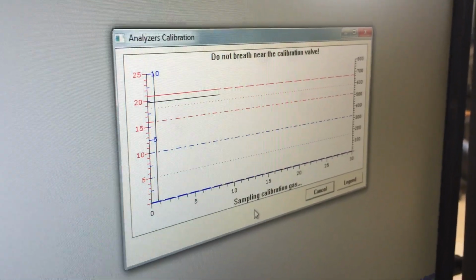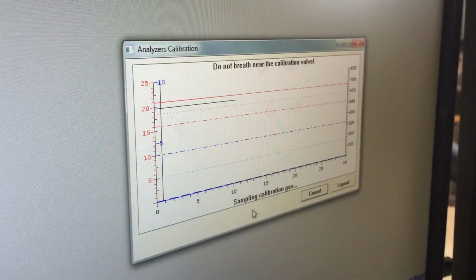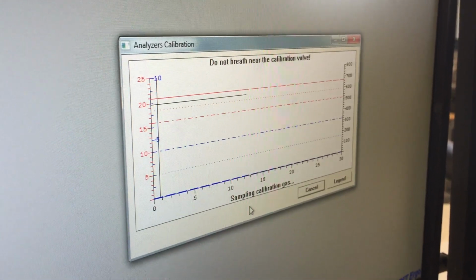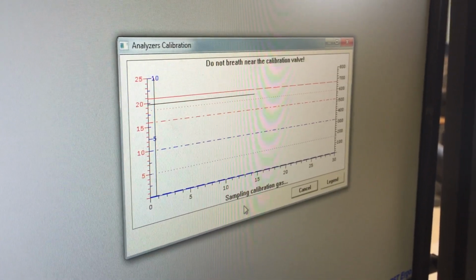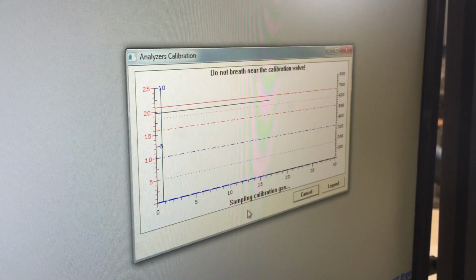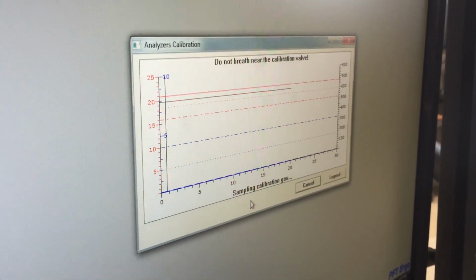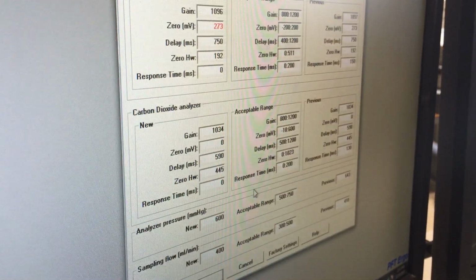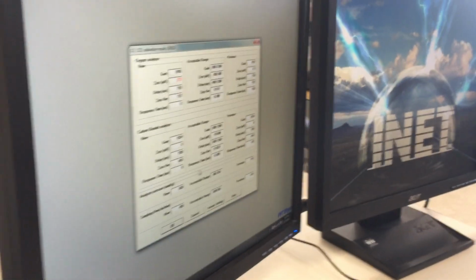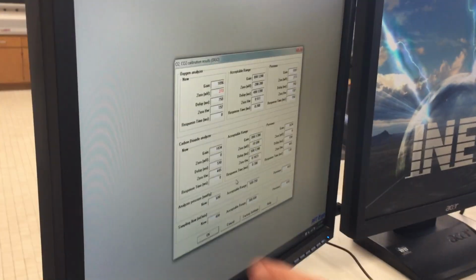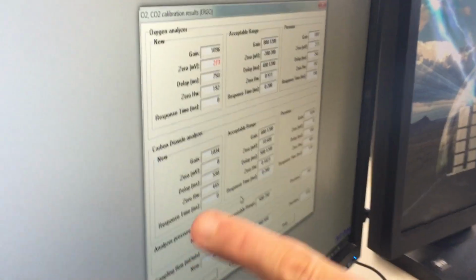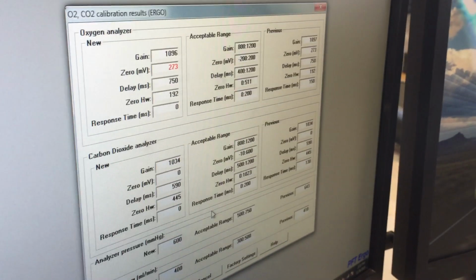We don't mess with the computer at this point. The software does its own thing. Once it gets all the way across, we can move forward. So at this point, we just wait. Again, remember, it takes about 10 to 15 minutes to actually calibrate the equipment from start to finish. So if you're taking that into account with the fact it takes 30 minutes for the unit to actually warm up, you need to make sure you give yourself adequate time. Now we see our calibration results. All of the black numbers mean everything is correct.